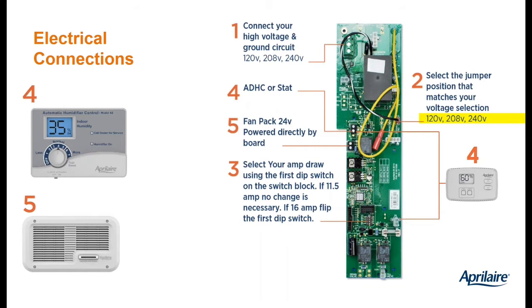The electrical side is very simple. Figure out what voltage you have available — 240 is ideal, many commercial applications only have 208, and 120 is okay if you've done the sizing. The transformer is a multi-tap transformer; make sure that tap is set to match your voltage. If it's set up for 240 and you're supplying 120, you'll only get 12 volts out of the transformer instead of 24 — so if your water valve isn't opening on a new installation, tech support will ask about the electrical supply and whether you moved the jumper wire.